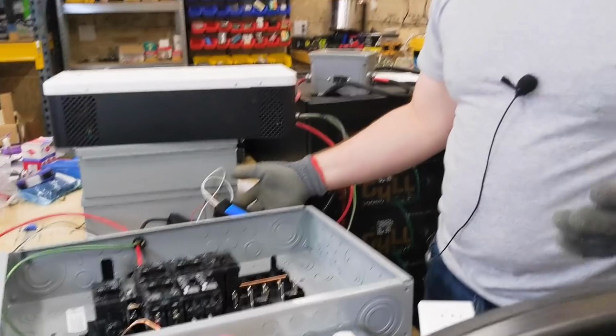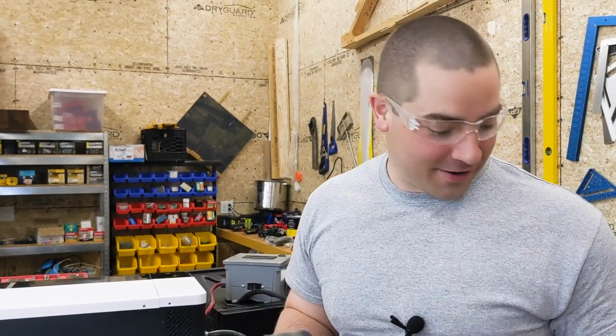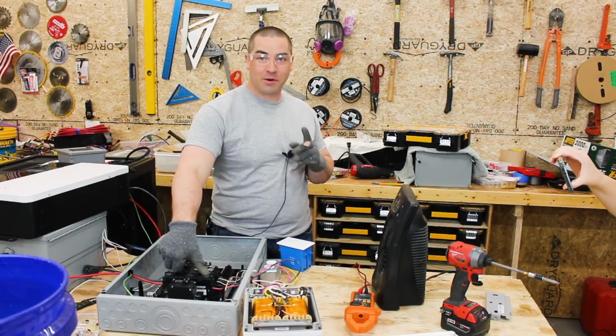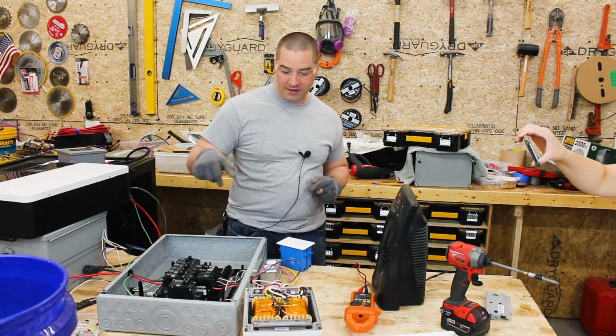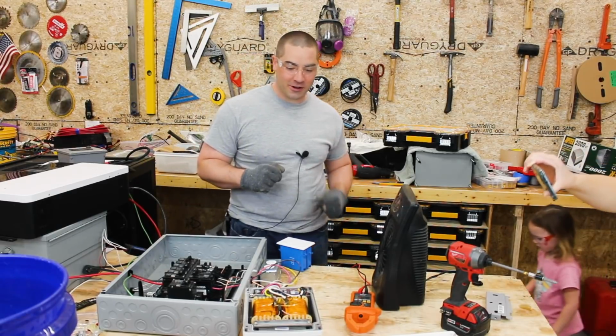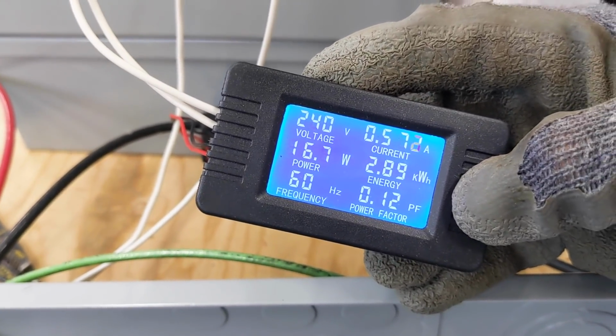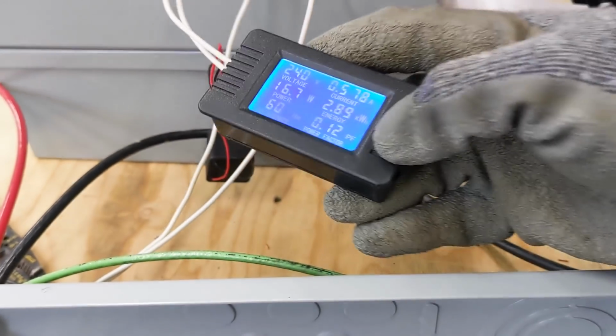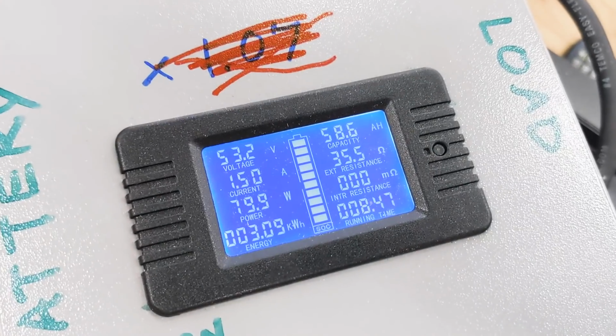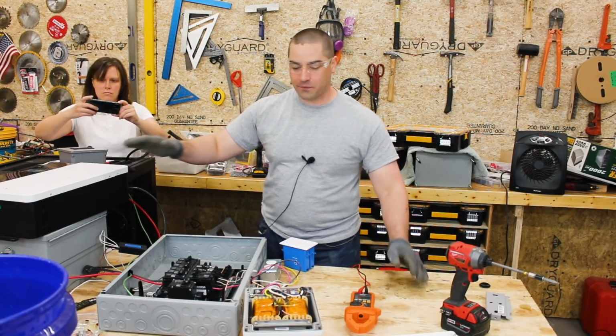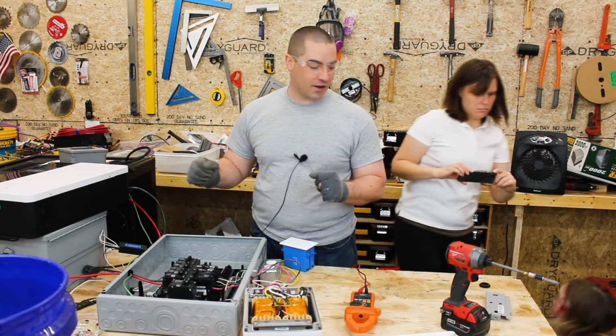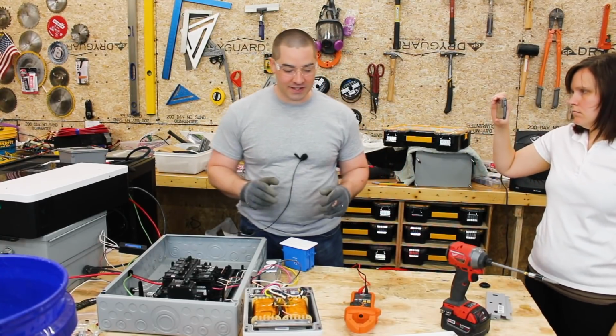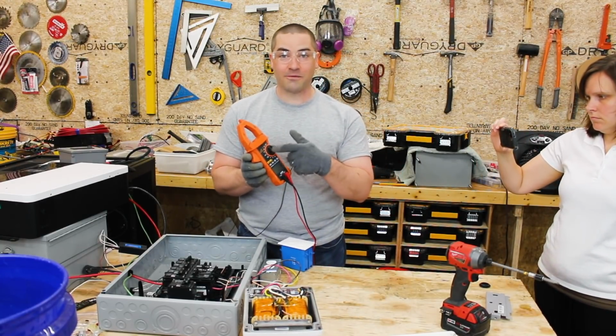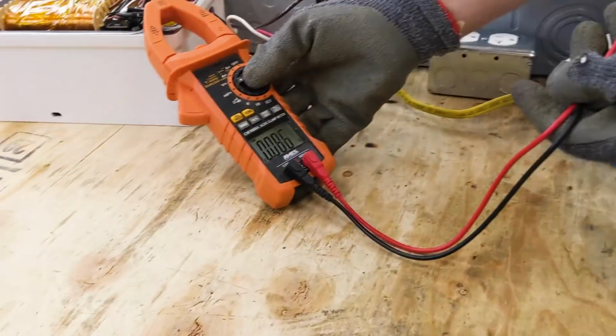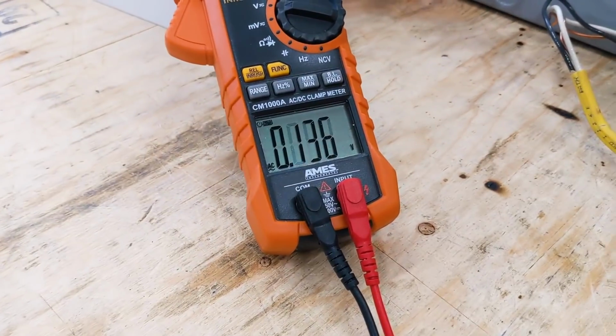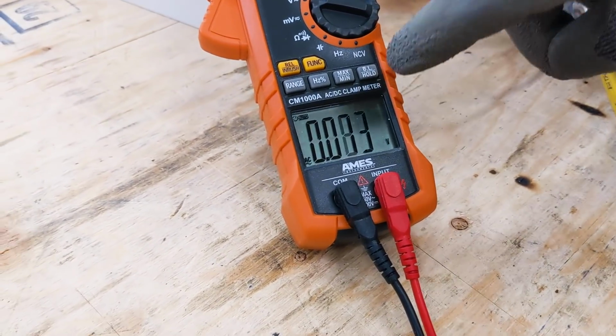So next item on the list, the auto transformer. Here we go with the auto transformer. We're going to find out how many watts this draws in idle. Oh, I hear a little hum coming off the auto transformer. So you can see the auto transformer is pulling 16.7 watts in idle. And we are drawing 80 watts. So 80 watts for the auto transformer being on and the inverter on. So this is really exciting. Now we're going to check our voltage here. So here's AC volts. Can you see that? Mm-hmm. Okay. So Elena here is going to be checking the voltmeter.